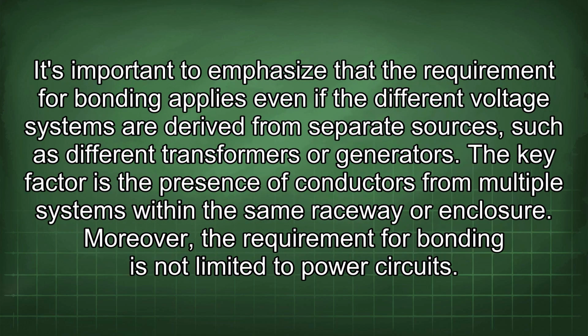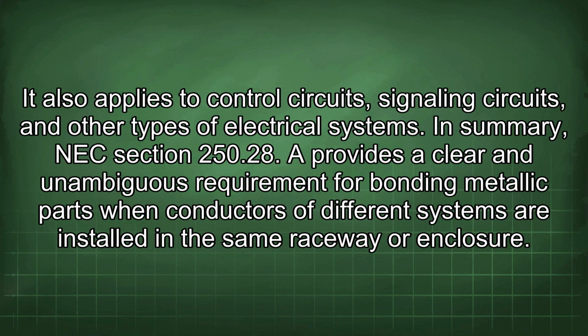It's important to emphasize that the requirement for bonding applies even if the different voltage systems are derived from separate sources, such as different transformers or generators. The key factor is the presence of conductors from multiple systems within the same raceway or enclosure. Moreover, the requirement for bonding is not limited to power circuits. It also applies to control circuits, signaling circuits, and other types of electrical systems.